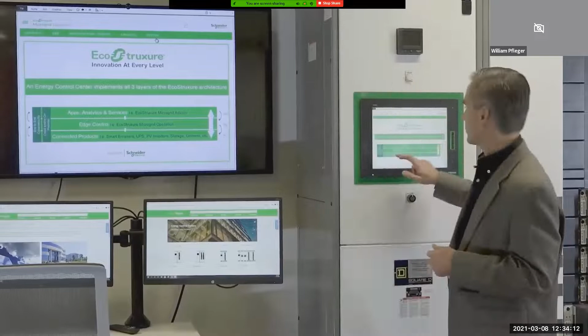So this is a simplified one-line diagram of our site before we put in the microgrid. And so you can see we have 2 MVA service coming in from the local utility and a lot of 480 volt loads. One very large load, which is a chiller. And that really ties into our peak load for the site. On a very hot summer day, we'll get up to about 1.5 megawatt peak.